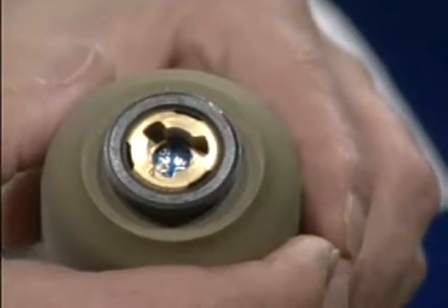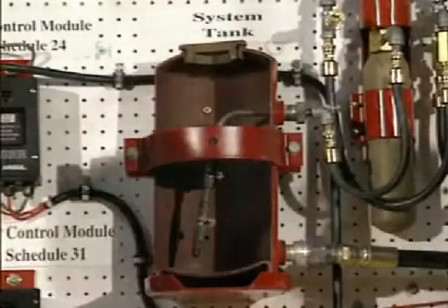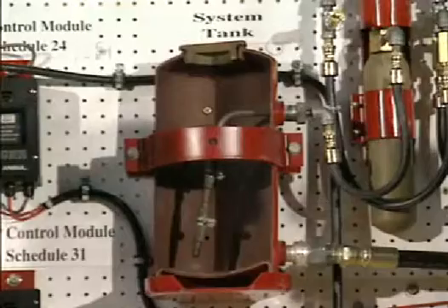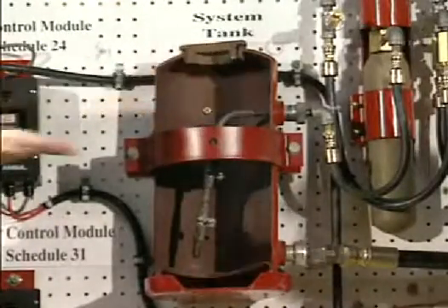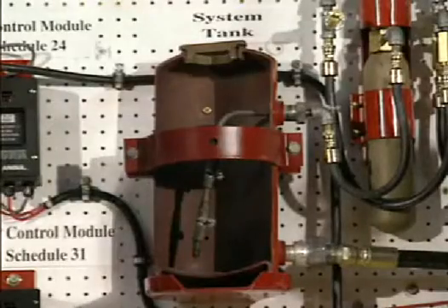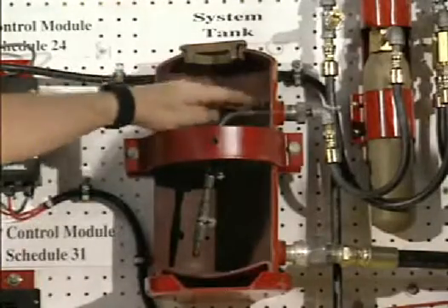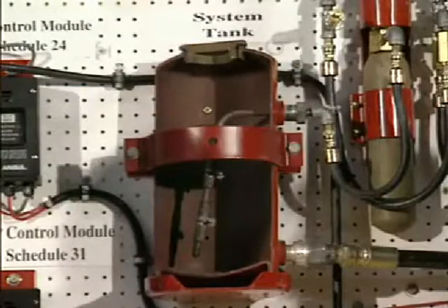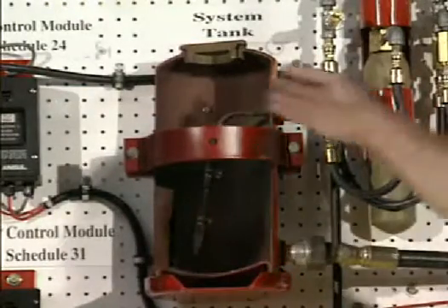Also, Brian, this actuation canister must have this seal. Ansul is blue. Each one of these tanks on the labels tells you how much chemical goes into these tanks. Poundage-wise. Open up the top. A lot of times, because of the chemicals settling, because the vehicle's moving, it should not be more than 3 inches below the top of the mouth of that canister. The mouth being the opening up here?